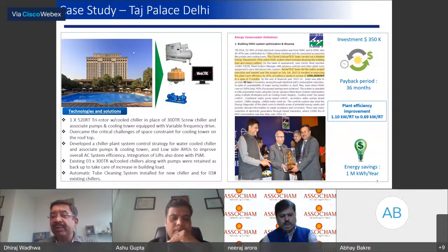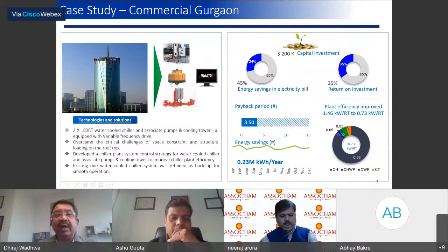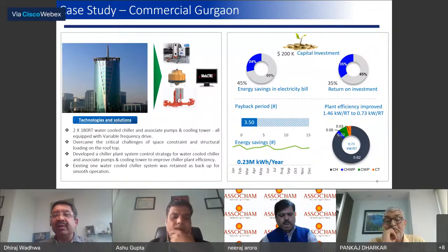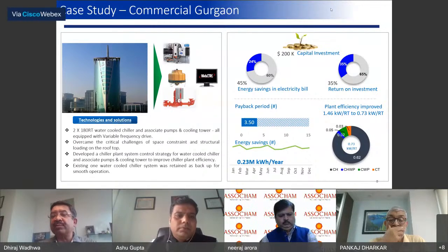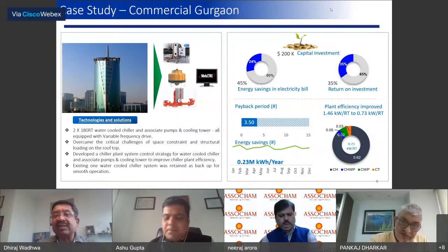Similarly, looking at another application, a commercial building in Gurgaon, we had the opportunity to do the same plant room audit activity. Here, it wasn't a 24/7 application but a 12-hour-a-day, 5-day-a-week operation, so the payback period was a bit higher, close to 3.5 years. But again, we were able to bring down power consumption from 1.46 to 0.73, a 50% reduction, improving efficiency and cutting energy consumption. That's the power of what an ESCO can do inside a plant room.